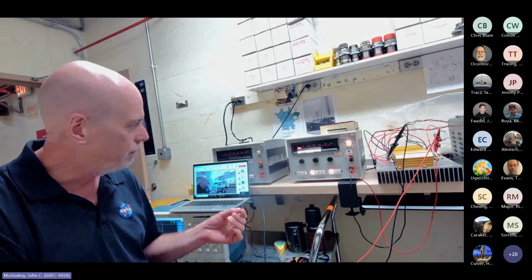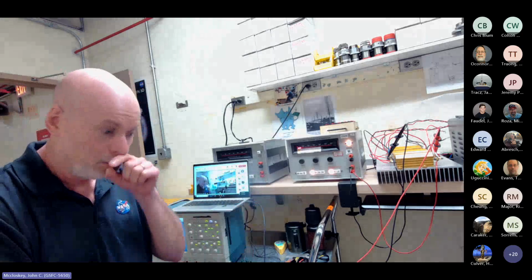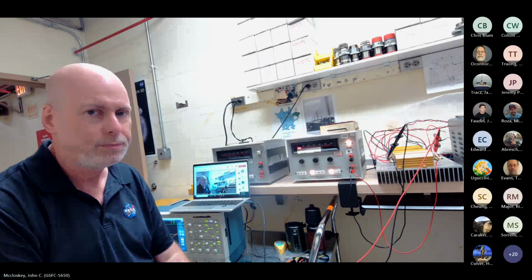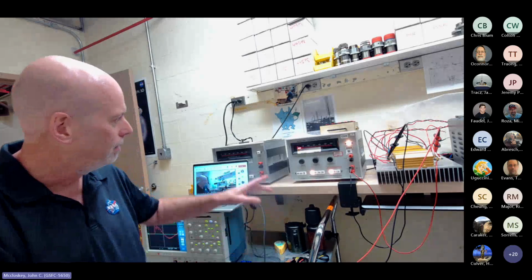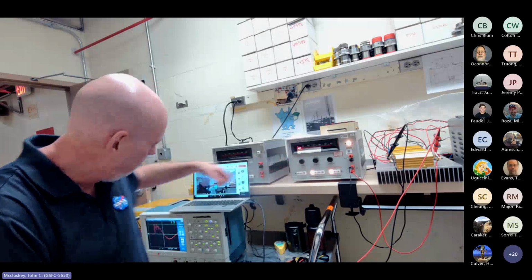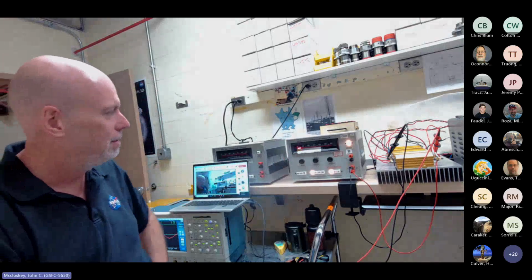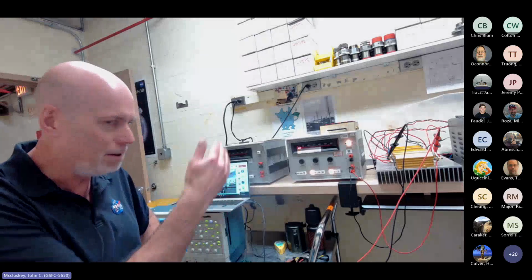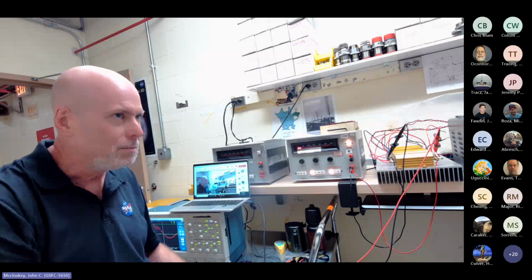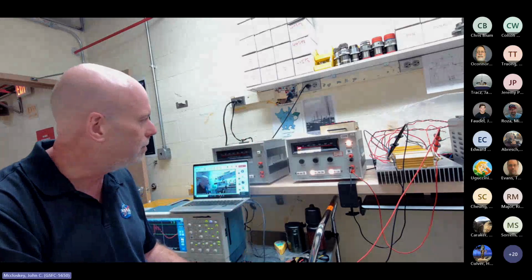But if you think there is enough of a concern to warrant the 10 microsecond pulse that we've been doing for years, that we know how to do. But again, 30 volts. Look, I've cranked this thing up to 60 volts here to get 30 volts. So there, the reflection seems to be basically cutting the amplitude in half. Sometimes the reflection will double the amplitude, and sometimes it takes away from it.